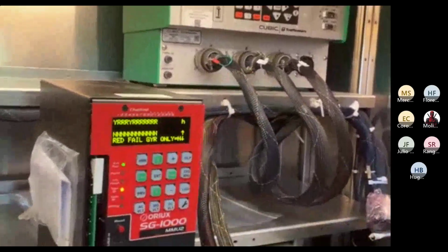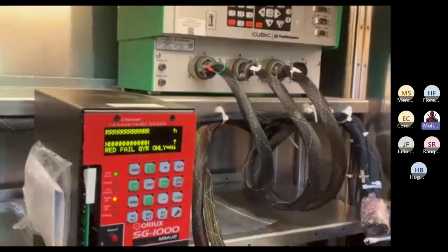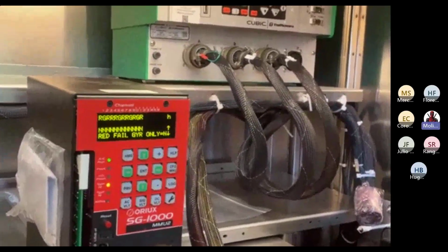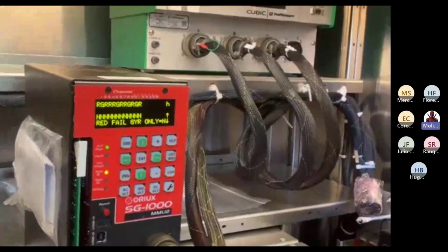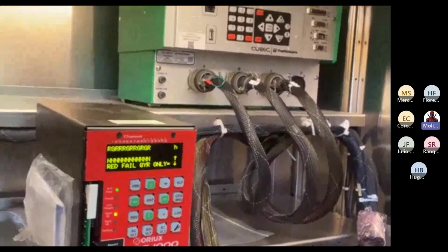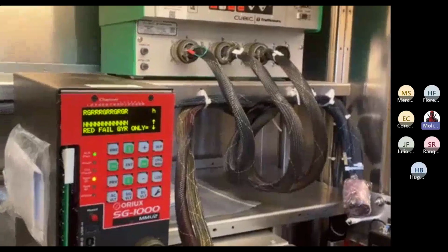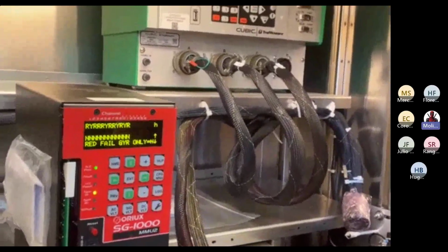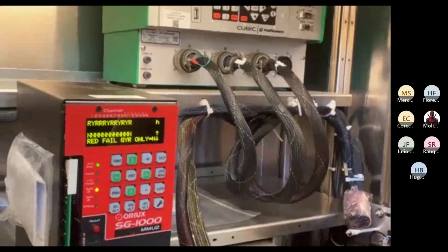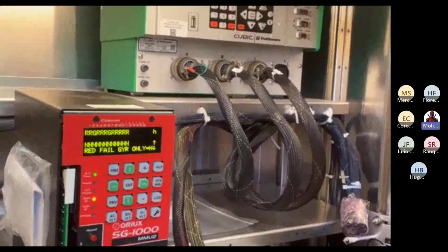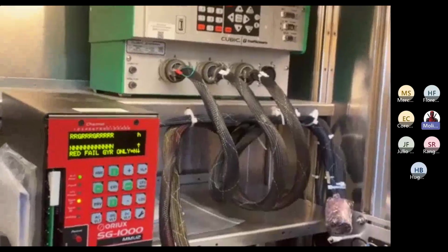So, for example, you have a doghouse signal, and you have two different channels, where you have one using the red, yellow, green, and one you're only using the green and yellow, no red, because it's sharing the red with another one. You can turn off the red fail monitoring just for the red on that channel you're not using the red on, for a 5 section. Correct, yes. So you can custom turn off specific outputs for red fail monitoring.